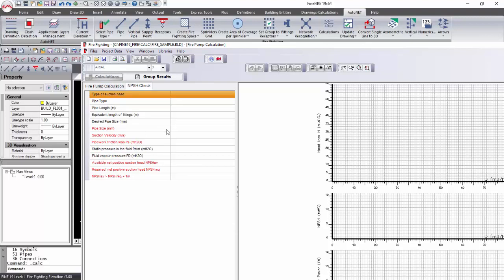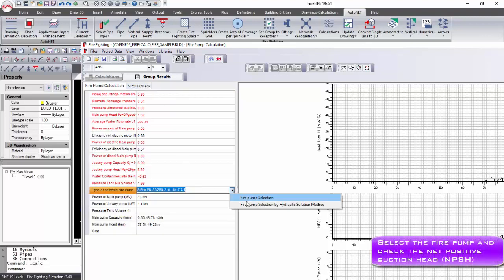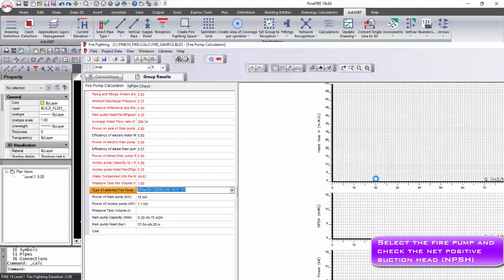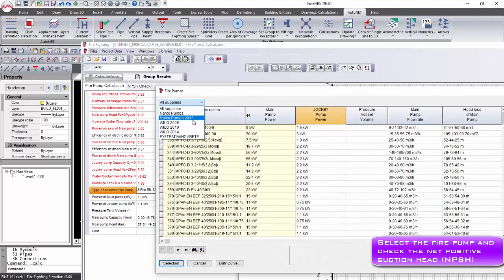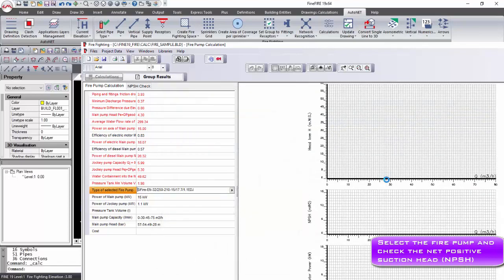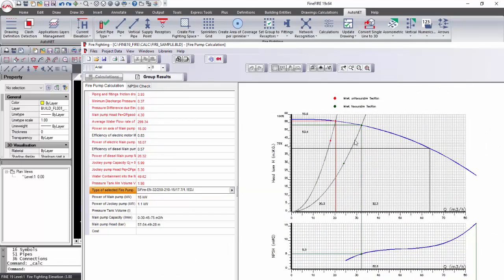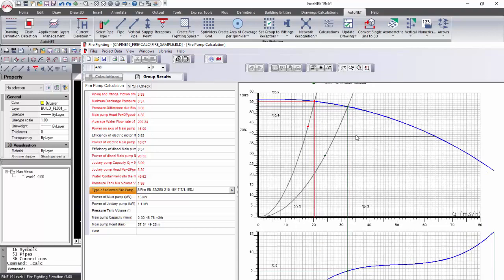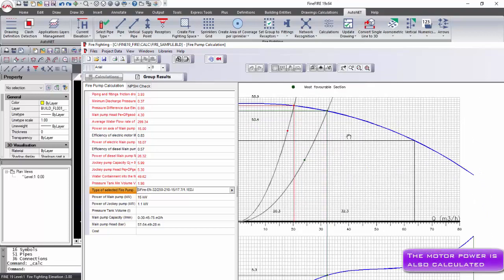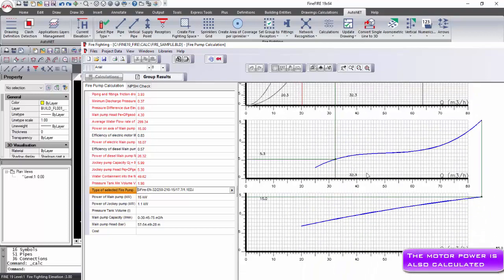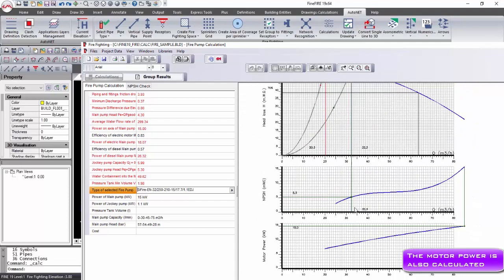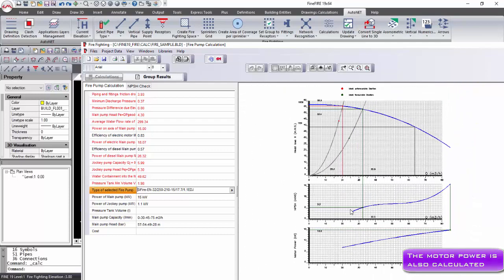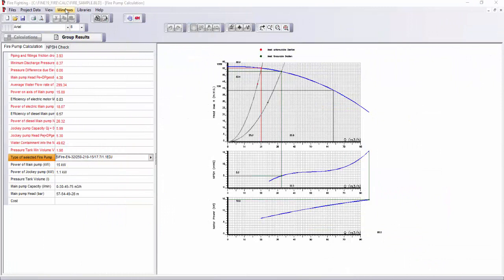With red color, the detailed calculation data of fire pump based on most favorable and most unfavorable groups appears. Decide the appropriate type of fire pump from Type of Selected Pump. When you select the fire pump, you can see on the right side of the window the pump's curve. You can also see the NPSH and motor curve under the pump curve. To continue, it is possible to search for any pipe sections in the stabilized flow condition that their velocity exceeds the maximum or they have no flow.